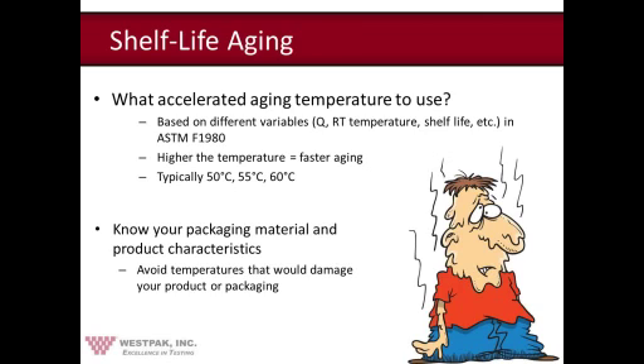And usually 60 to 65 C is a safe upper limit. But the bottom line is you should know your product and your packaging characteristics and avoid any temperatures that would damage them. Herb, you want to add to this? Thanks, Kevin. A question that arose during our earlier webinar on the same topic involved the use of humidity with the temperature in an accelerated aging process.